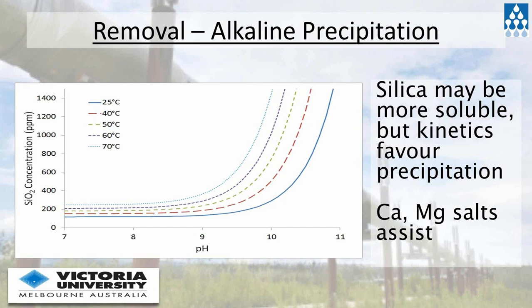So the extra solubility comes about from effectively partially dropping the silica out of solution, is one way to think about it. And the problem is these techniques are used quite a lot, high pH, to drop and remove silica from solution. A lot of it though comes down as well to the presence of different salts in there and dropping out silicates, but not just dropping out silicates. Importantly, magnesium hydroxide is a wonderful sorbent for silica. So if we can manage to form enough magnesium hydroxide at the same time, then we can absorb a lot of silica and drop that out of solution as well.